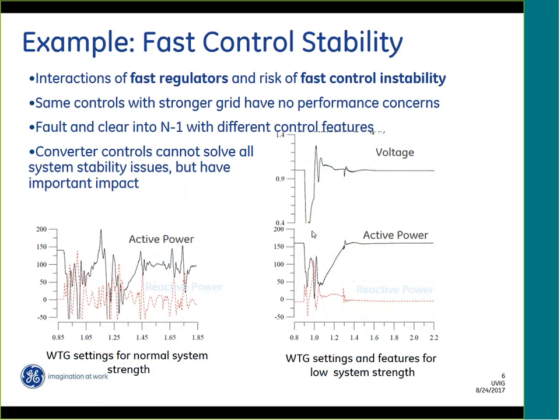When that happens, we have an interaction between the fast regulators, between the wind turbines and the SVC in this case. So you can see the black line is active power, and the red line is reactive power. So you can see relatively fast oscillations. These oscillations would typically be somewhere between 10 to 20 hertz, and have to do with the inner current control loops, or occasionally could be related to fast voltage control loops. That interaction, I don't mean to say that you always have this type of problems with SVCs, or you always have this type of problems with wind turbines, but it's something that could happen.